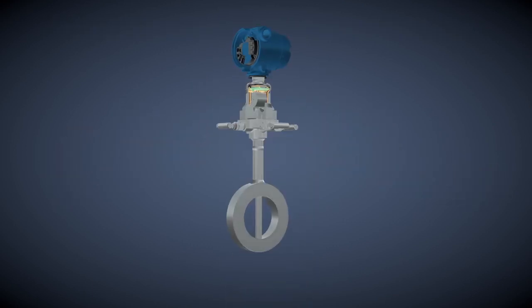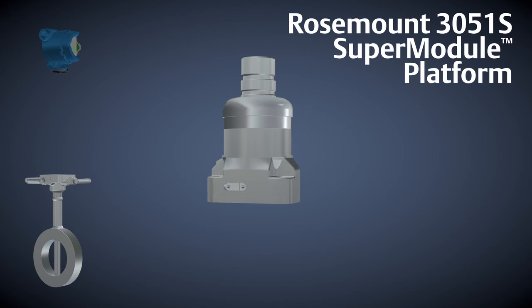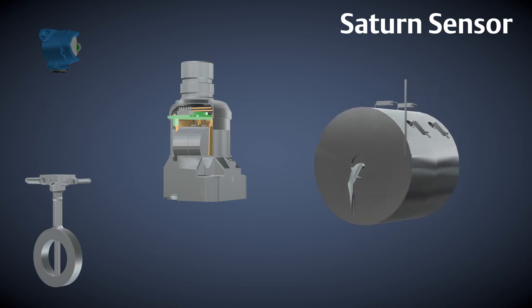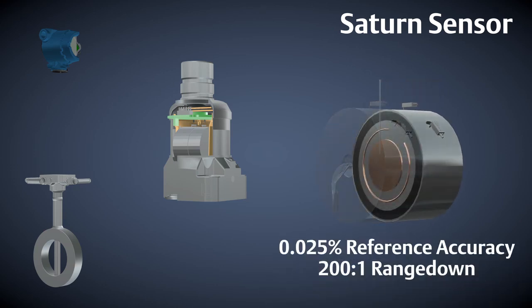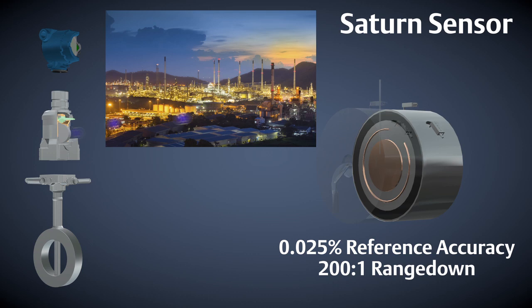The heart of this scalability begins with the Rosemount 3051S supermodule platform, which is the industry's most advanced pressure technology architecture. Inside is the patented Saturn sensor, which has an additional sensing ring that provides up to 0.025% accuracy and 200 to 1 range down capabilities, allowing you to use fewer models to cover all your pressure ranges.